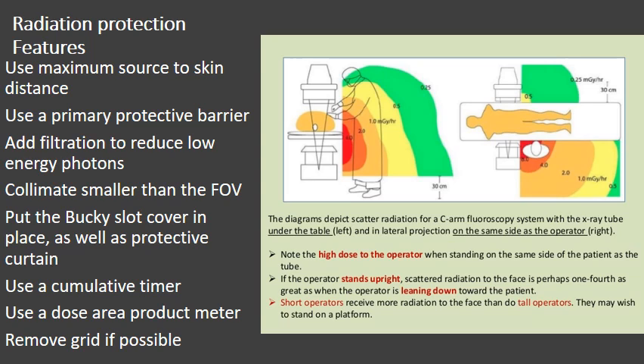There's also a Bucky slot that refers to the space that opens when the Bucky is moved to the end of the table in fixed units. The space should have a cover of about 0.25 millimeters of lead equivalent. This normally moves into place automatically.